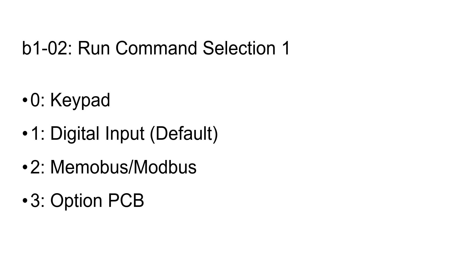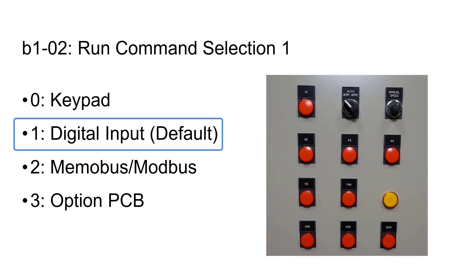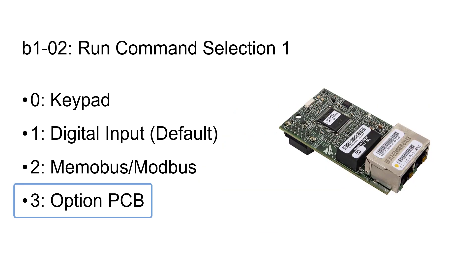There are four options. Setting 0 is the keypad. Setting 1 is a digital input, such as switches or buttons. Setting 2 is MemoBus/ModBus. And setting 3 is the communication option card, such as the Ethernet card, to receive commands over a network.